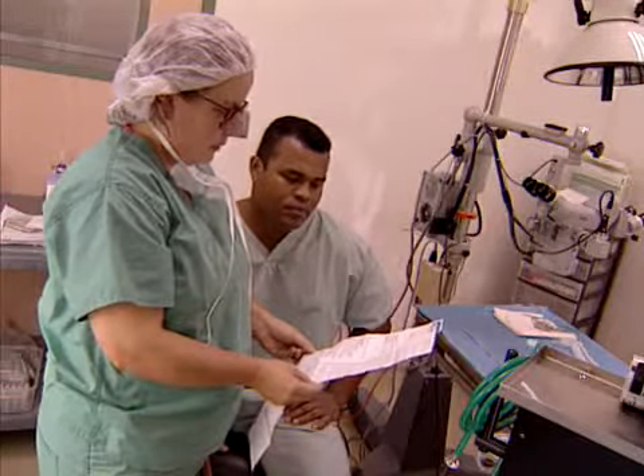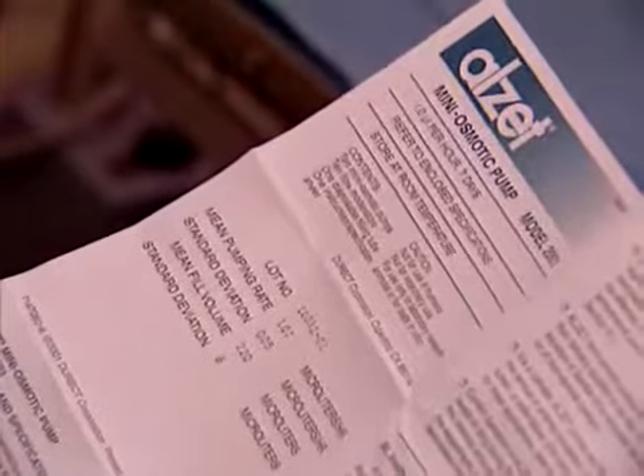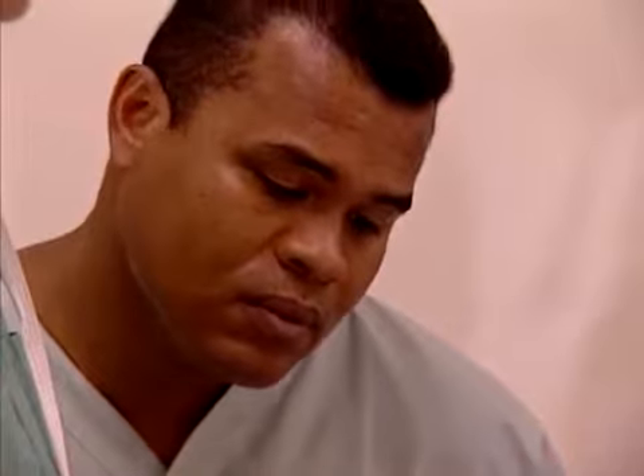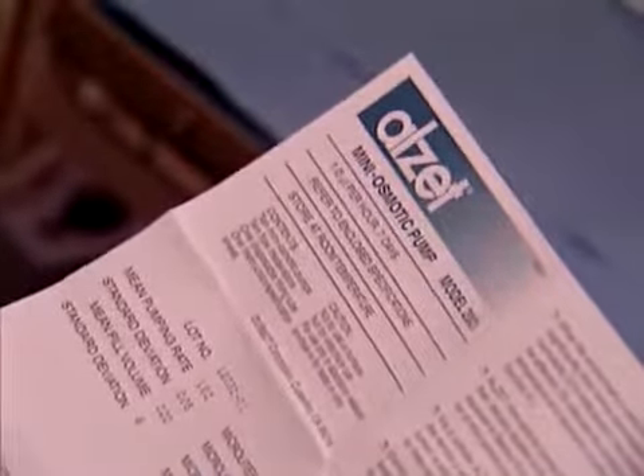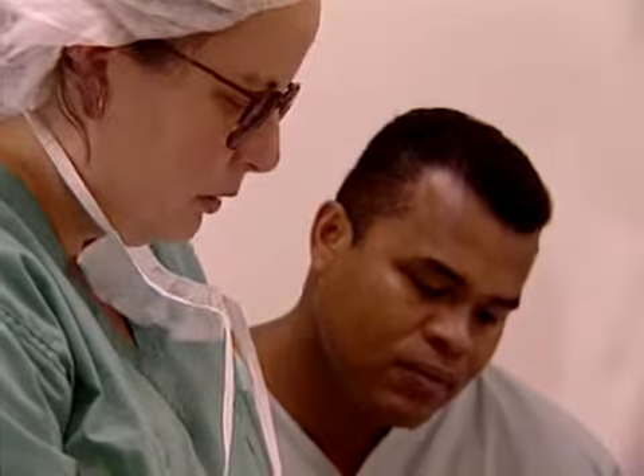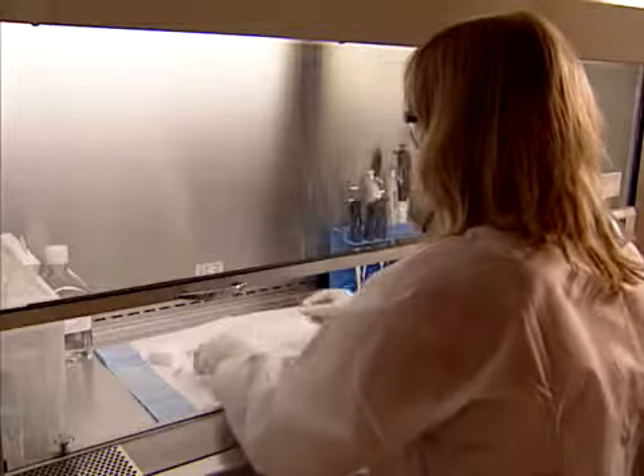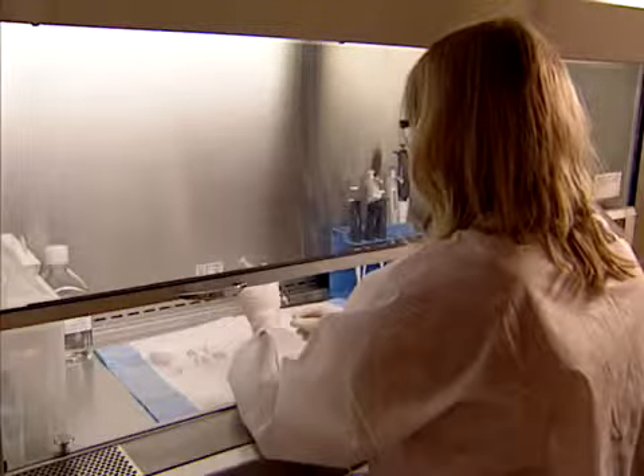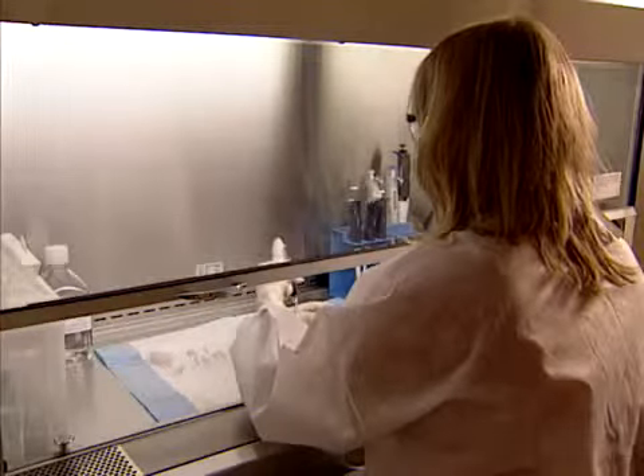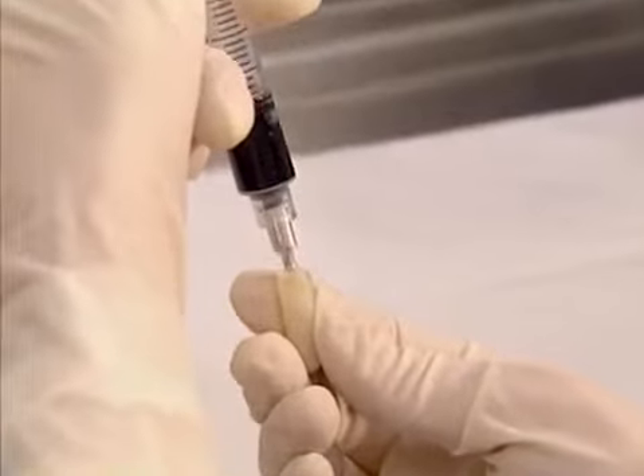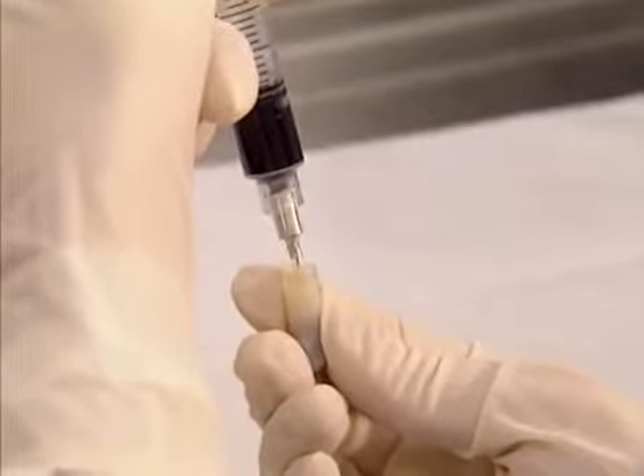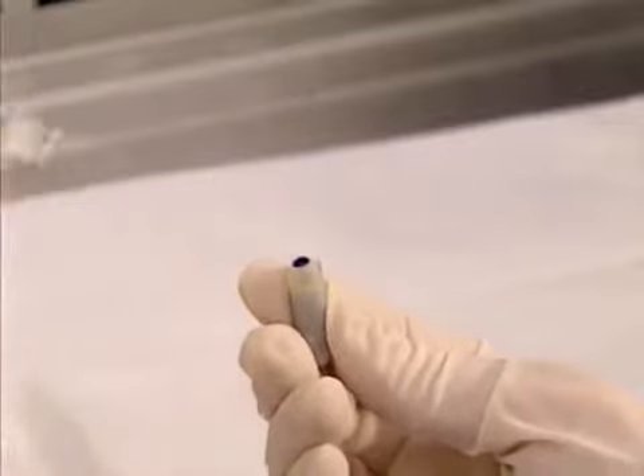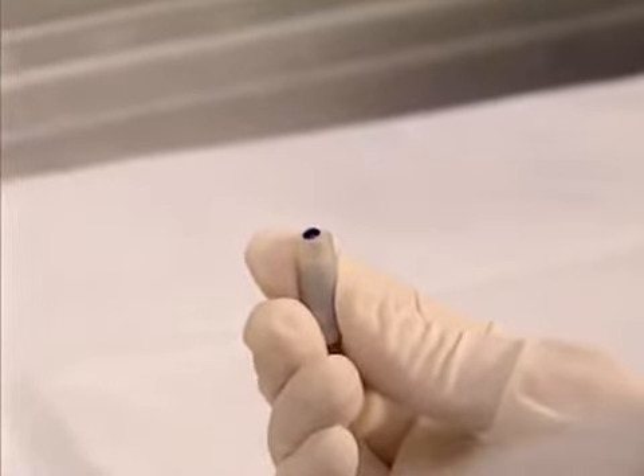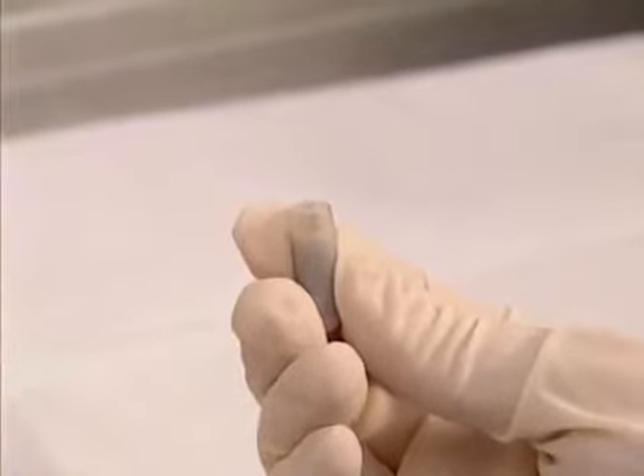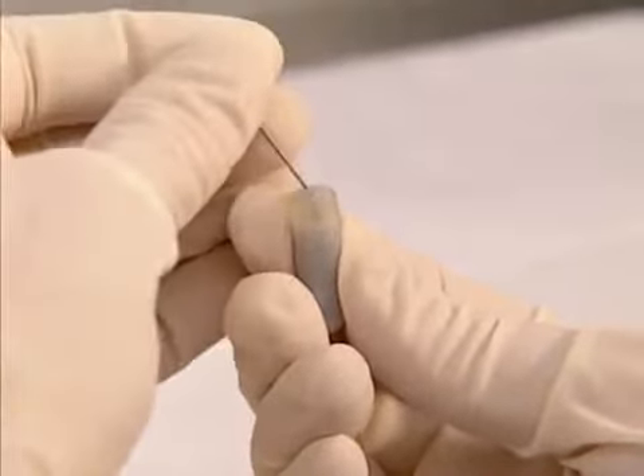Once you have selected the appropriate pump, familiarize yourself with the detailed instructions included in the package. Take particular note of the lot-specific fill volume and release rate. Carefully read the instructions on how to fill the pump. The pumps are packaged under sterile conditions. Using aseptic technique, fill the pump in a laminar flow hood. Use the filling tube that is supplied to fill the pump completely, making sure there are no air bubbles. Remove the tube and set the flow moderator in place.